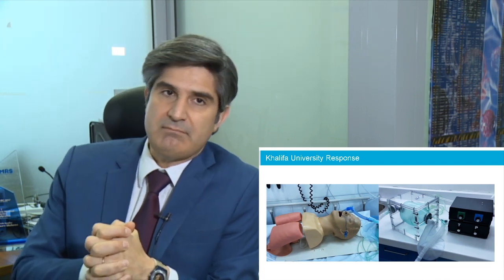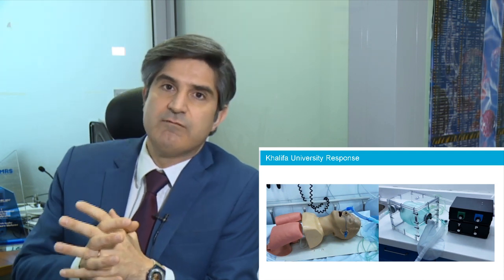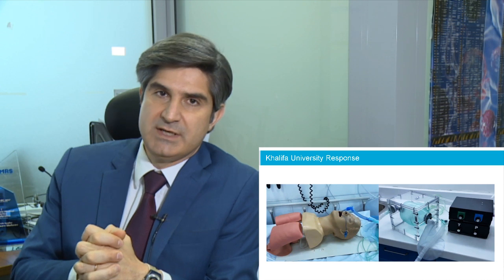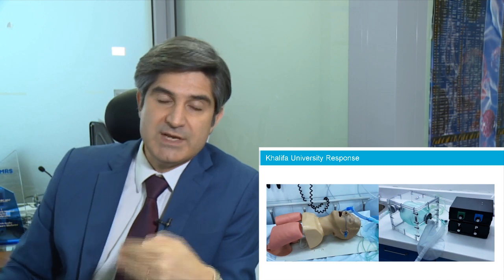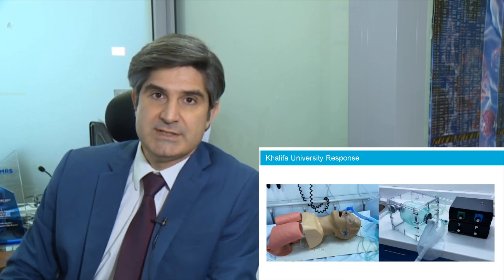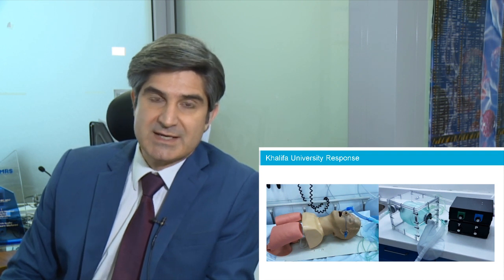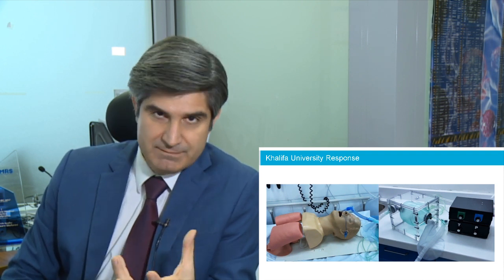So you see 4 dials in this machine, and these 4 dials are taking care of 4 key parameters in assisted ventilation. One parameter is the frequency, so how many breaths per minute you give to the patient. Another parameter is pressure. So we need to take care that pressure is not too low nor too high, not to create damage to the lungs and to provide ventilation.